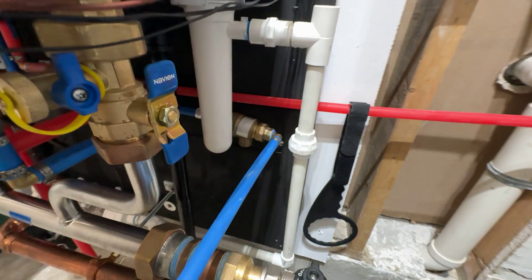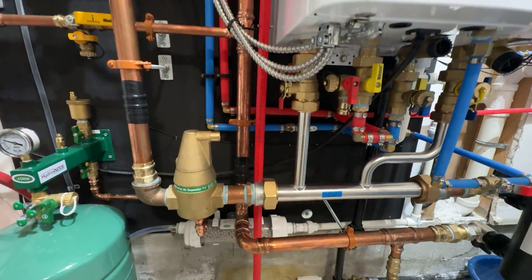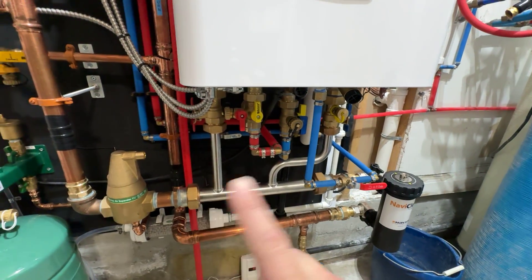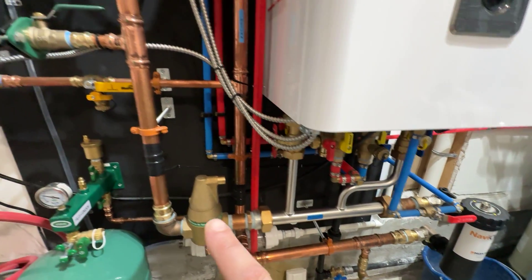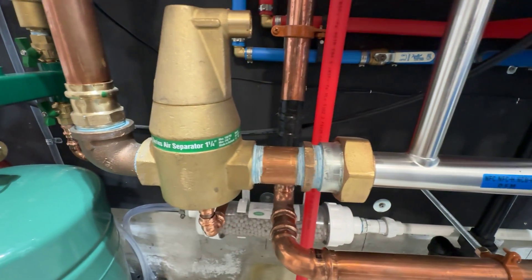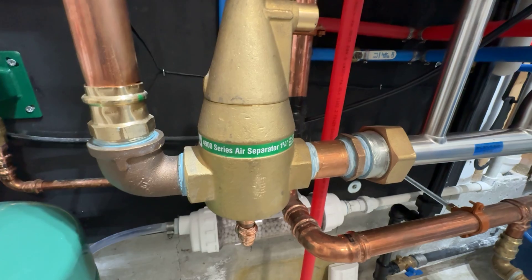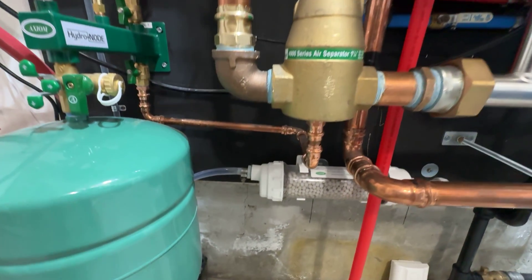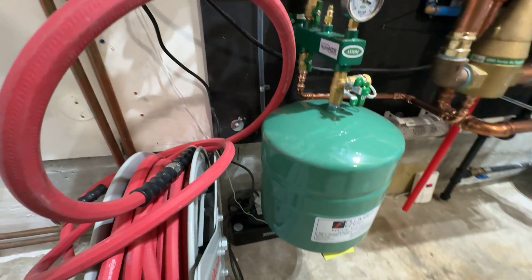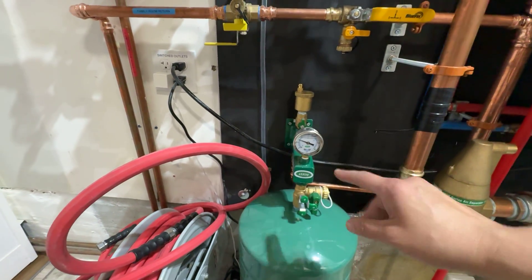The Watts check valve is going to prevent backflow to the potable water. This is the primary loop, and then we're getting into the secondary loop here. I went with the Taco 4900 series air separator, inch and a quarter. That's piped over to my Axiom HydroNode. This thing's pretty cool — it's worth the money. It comes with all the fittings, the pressure gauge, and the expansion tank service valve here.